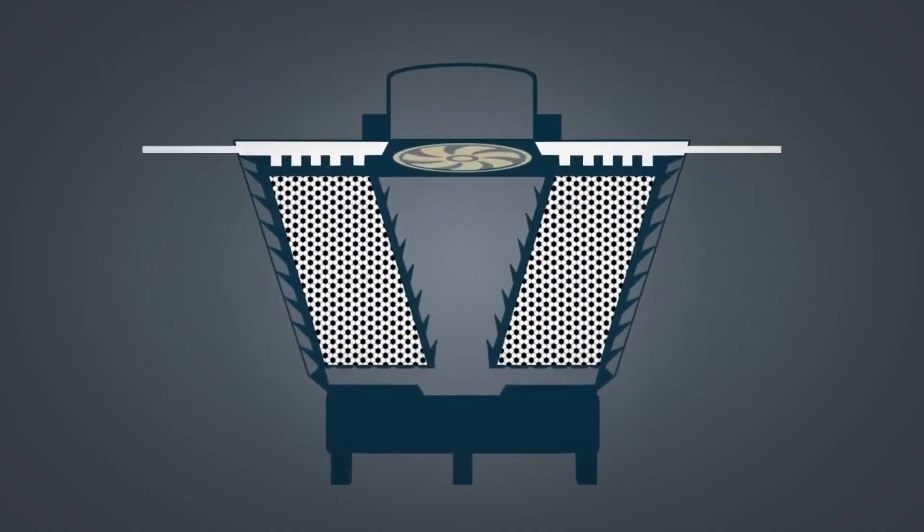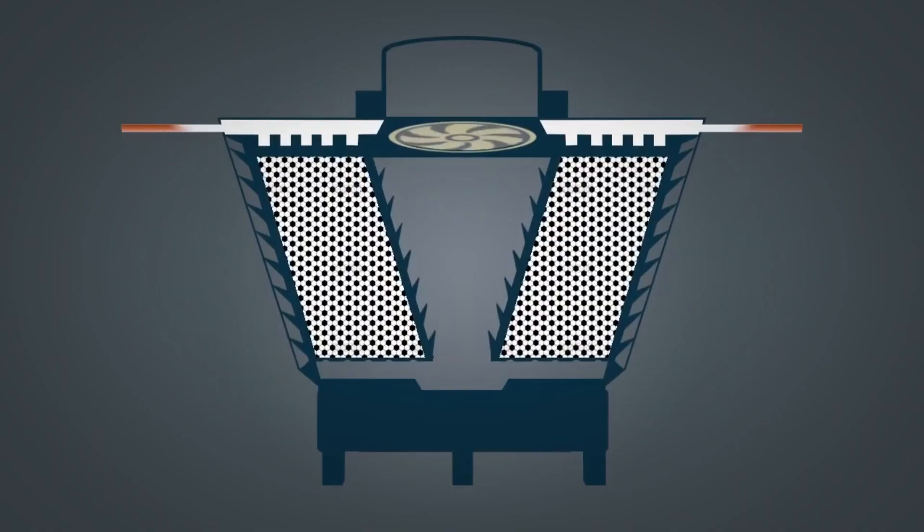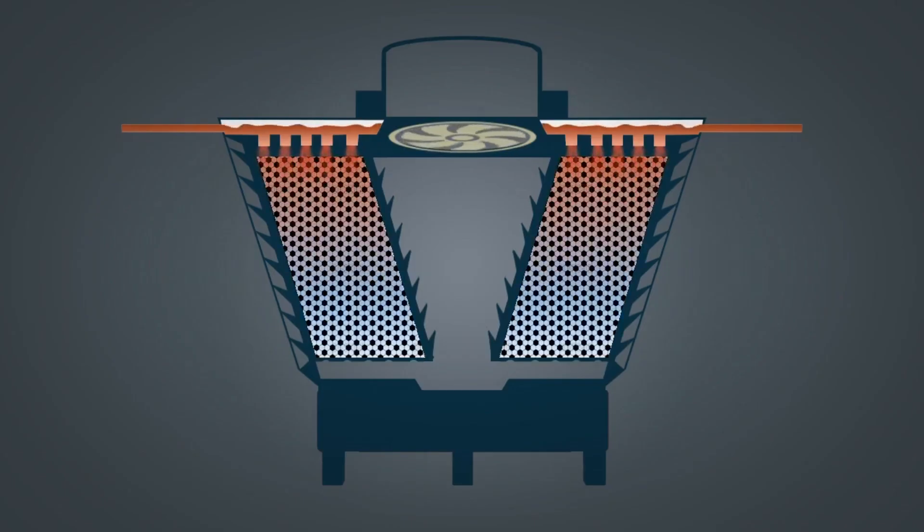In case of a cross flow cooling tower, hot water is sent through a water inlet to the cooling tower. Then, it is distributed on the fill media through water distribution system. The gravity causes the water to cascade down across the fill media. The fill media breaks the water stream into smaller water droplets creating a large surface area for heat transfer.